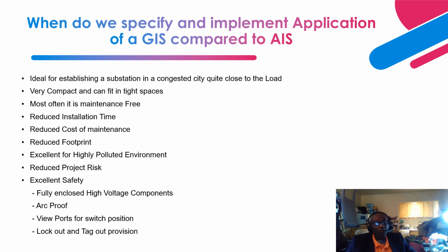As you know, sometimes there is a highly polluted environment. And where is a highly polluted environment? That is from an industrial facility, oil, gas, and other industries out there that emit a lot of pollutants: salty pollutants, oil, dust, and sand, etc. So if you have an air insulated substation, what happens? Basically these pollutants are going to impinge on the insulators, the apparatus insulators, the support insulators, the equipment themselves, and also all the live connection points.